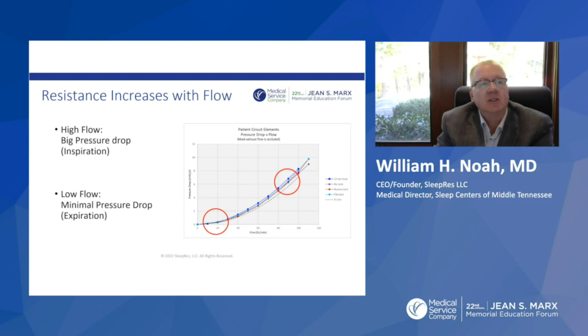So let's talk about how this works. On inspiration, there's real high flow because you see the exhaust there in the middle. You've always got to have exhaust, because to have pressure, you've got to have exhaust; the pressure in the circuit is what's driving the exhaust. You remember, as in the second question we did, the patient's pressure went from 13 to 16. Well, their exhaust flow went up because there's more pressure driving that flow. See, the room air is 0. If it's 13 centimeters, the pressure gradient is 13 to 0 going out through those little holes in the mask. And if it's 16, you've got much higher flow. So the exhaust flow is always there.